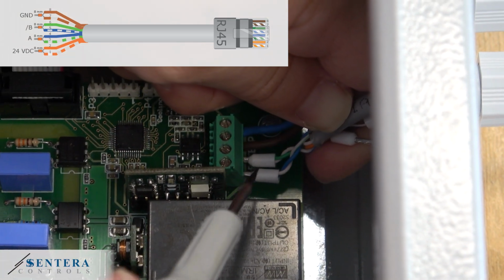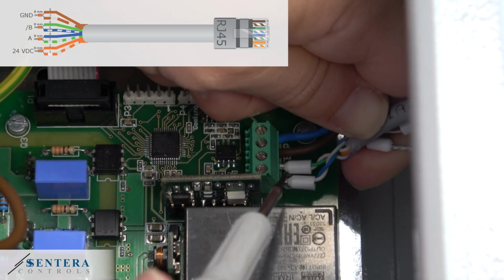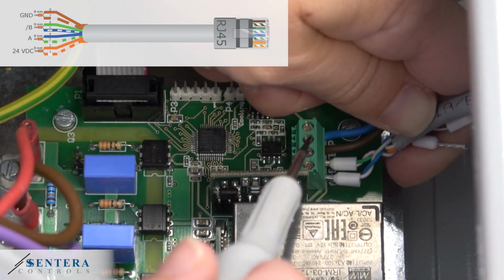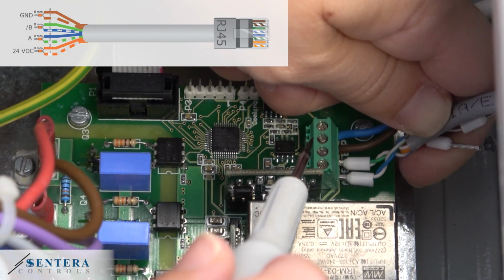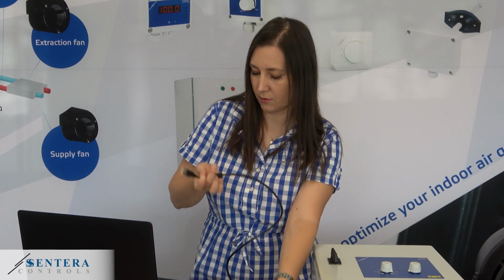The blue wire twisted with white and green wire is for A signal, while the green one twisted with white and blue is for Modbus B signal. The other side of the UTP cable that's crimped with the RJ45 socket needs to be plugged into Sentera's converter. Plug in the crimped cable into the converter and the USB at the other side to connect to your computer.